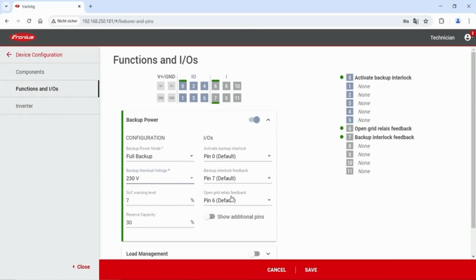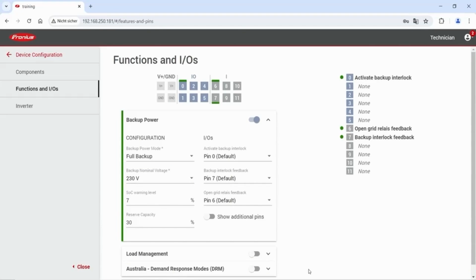On the right hand side you need to configure your digital IOs. With that, the activation of the backup power functionality is possible. In our case, please make sure to always use the default values. So in this case for backup interlock feedback pin 7, and for the open grid relay feedback pin 6. Please also note, for the manual switchover, no digital input I/O for the activation is needed. So in this case the pin I/O 0 is not needed for our solution, since we are using the manual switchover. The overview is also shown on the right hand side, and when you have configured your digital inputs you can hit the save button to conclude the commissioning system.